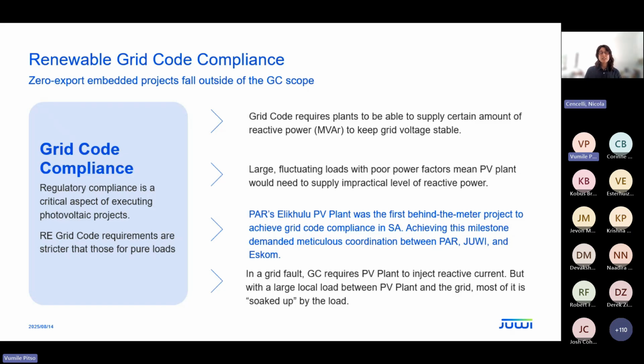So renewable energy grid code compliance - this is one of the biggest hurdles we have to comply with. For example, the Elikhulu PV plant, which Kobus might speak to, that's what we built with Pan-African Resources. That was the first behind-the-meter project in South Africa which could achieve grid code compliance. We did need to make quite a few changes to the grid code there, or look for exceptions. Effectively, the reason it was so tough is because the grid code doesn't quite apply to behind-the-meter generators, and especially not in this case, since it was a zero export generator.